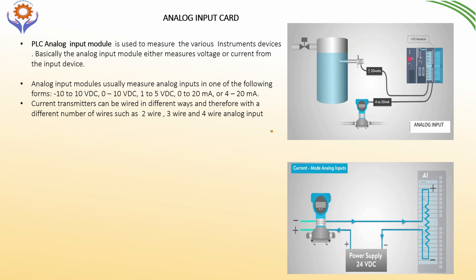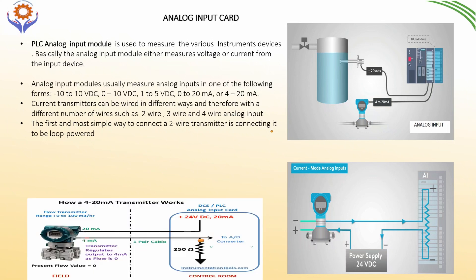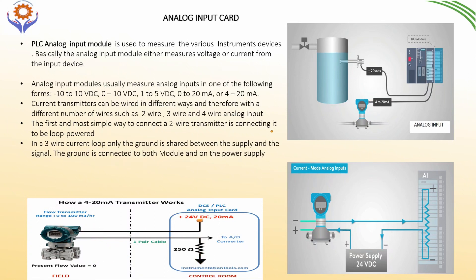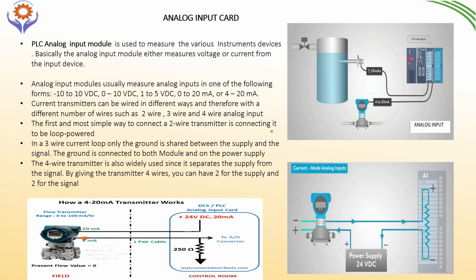Current transmitters can be wired in different ways with different numbers of wires: 2 wires, 3 wires, and 4 wires. The simplest way is 2-wire, connected as a loop-powered device. In a 3-wire current loop, only the ground is shared between the power supply and the signal — the ground is connected to both modules on the power supply. The 4-wire transmitter is widely used to separate the power supply and the signal: 2 wires for power supply and 2 wires for signal.